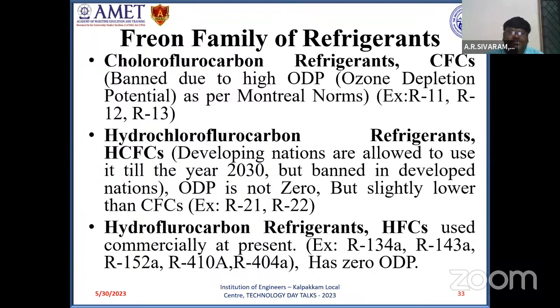Freon family of refrigerants actually has three categories. First type, chlorofluorocarbon. When considering any refrigerant from an environmental point of view, two things are considered. One is ODP, ozone depletion potential, and the next one is global warming potential. So coming to CFCs, they have high ozone depletion potential. According to the Montreal norms, CFCs are banned completely because they have high ozone depletion potential, and right now we are not using any CFCs. Typical examples of CFCs are R11, R12, and R13.